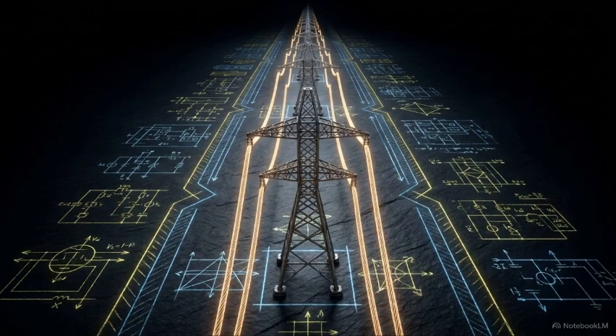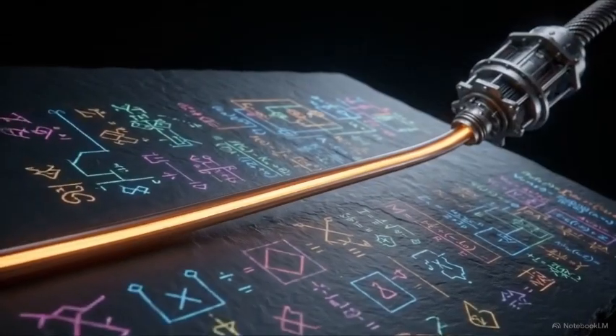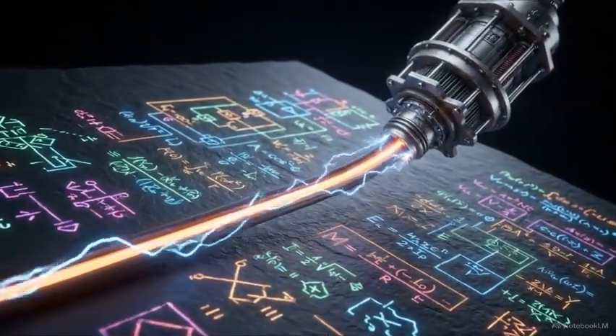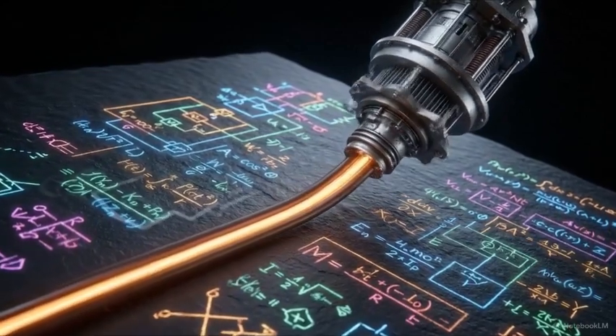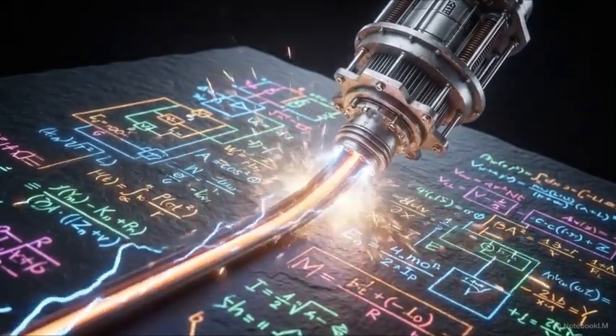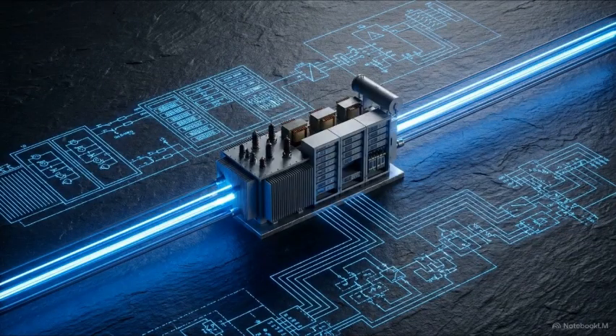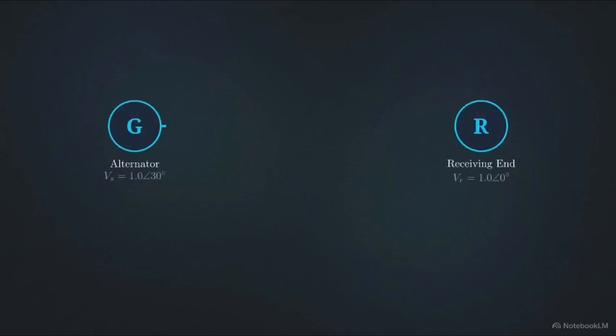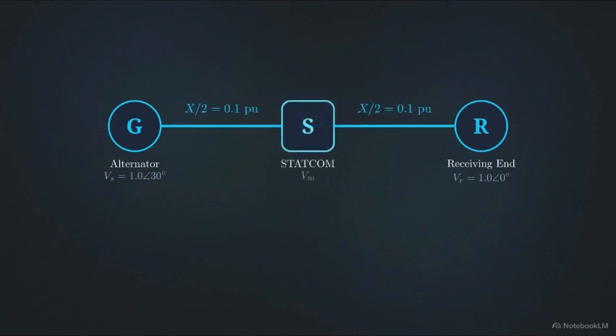Over hundreds of miles, continuous transmission lines accumulate so much natural inductive reactance that standard series capacitors lose their effectiveness. To solve this, grid operators utilize midpoint compensation. They deploy active reactive elements, like STATCOMs, precisely in the center of the grid to actively split the transmission line into smaller electrical segments. This diagram shows a long line with a total reactance of 0.2 per unit.